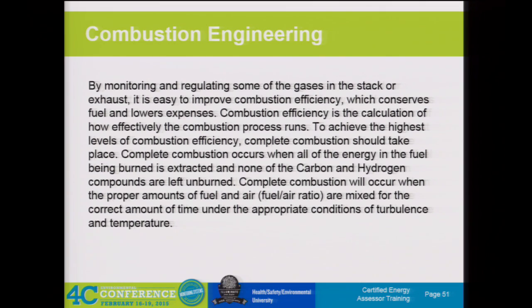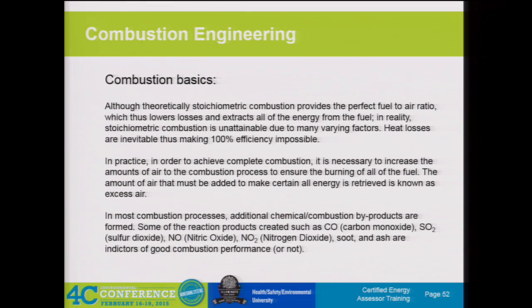Complete combustion occurs when all of the energy in the fuel is burned and extracted, and none of the carbon and hydrogen compounds are left unburned. This is the ideal scenario—in practice, it's not necessarily achievable. The air-to-fuel ratio is very critical in achieving or getting close to the ideal condition of complete combustion. Although stoichiometric combustion provides the perfect fuel-to-air ratio—lowering losses and extracting all energy from the fuel—in reality these conditions are unattainable due to heat loss and other inefficiencies in the system.